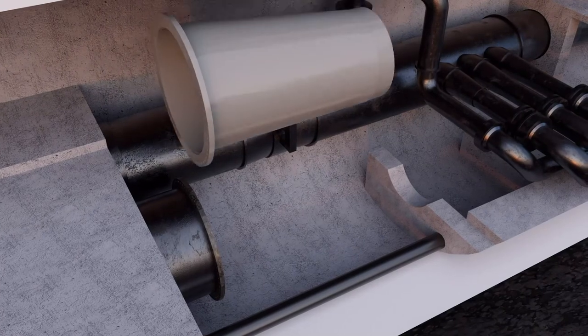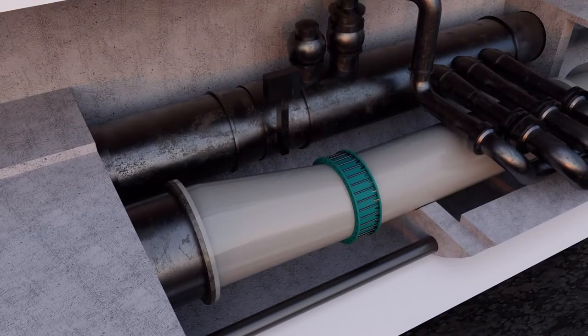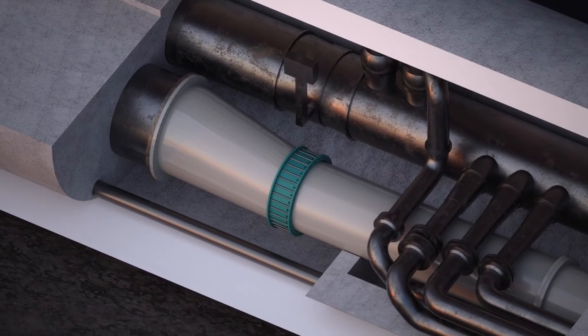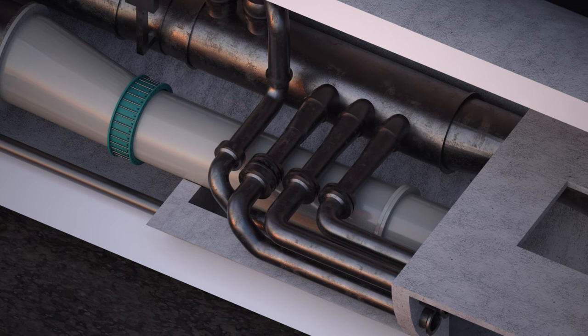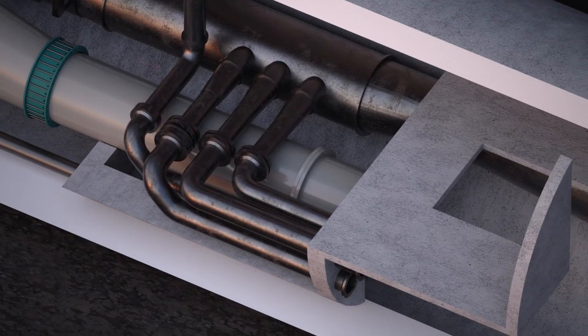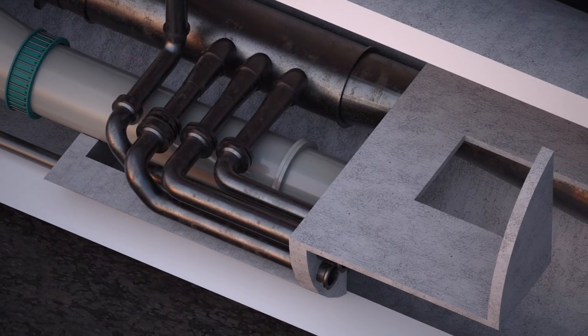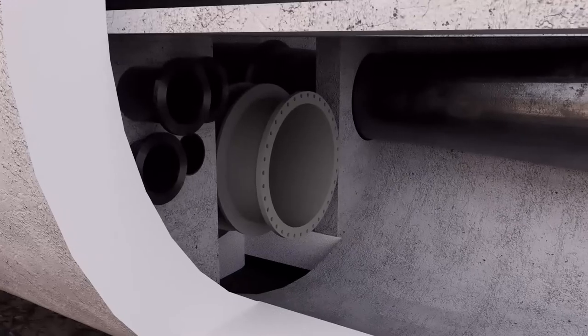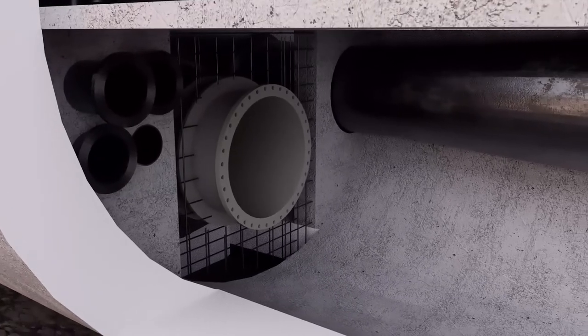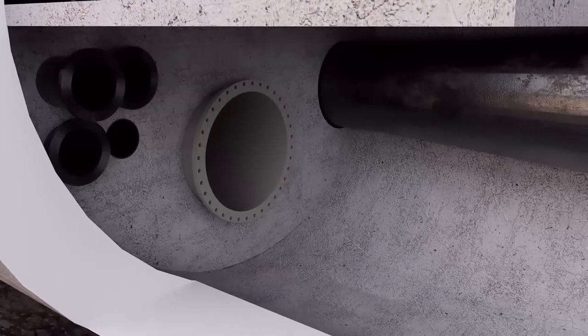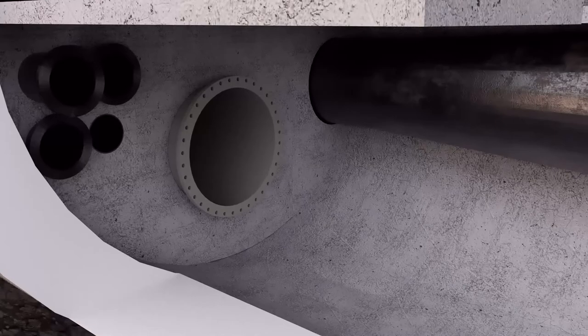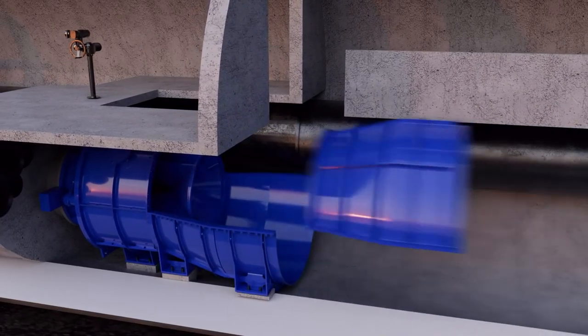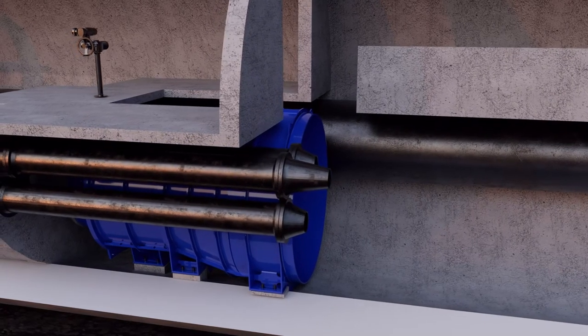Back in the hydro room, a new penstock reducer was added. The new reducer is eccentric rather than concentric and shifted the center line of the penstock to allow space for the much larger VAG-supplied hollow cone valve. A new section of 56-inch penstock was installed and connected to the reducer with a rubber coupling. Concrete was poured to construct a new thrust block capable of holding the valve against the immense force of the water that will flow through the low-level outlet tunnel. The new hollow cone valve was finally ready to be installed, completing this section.